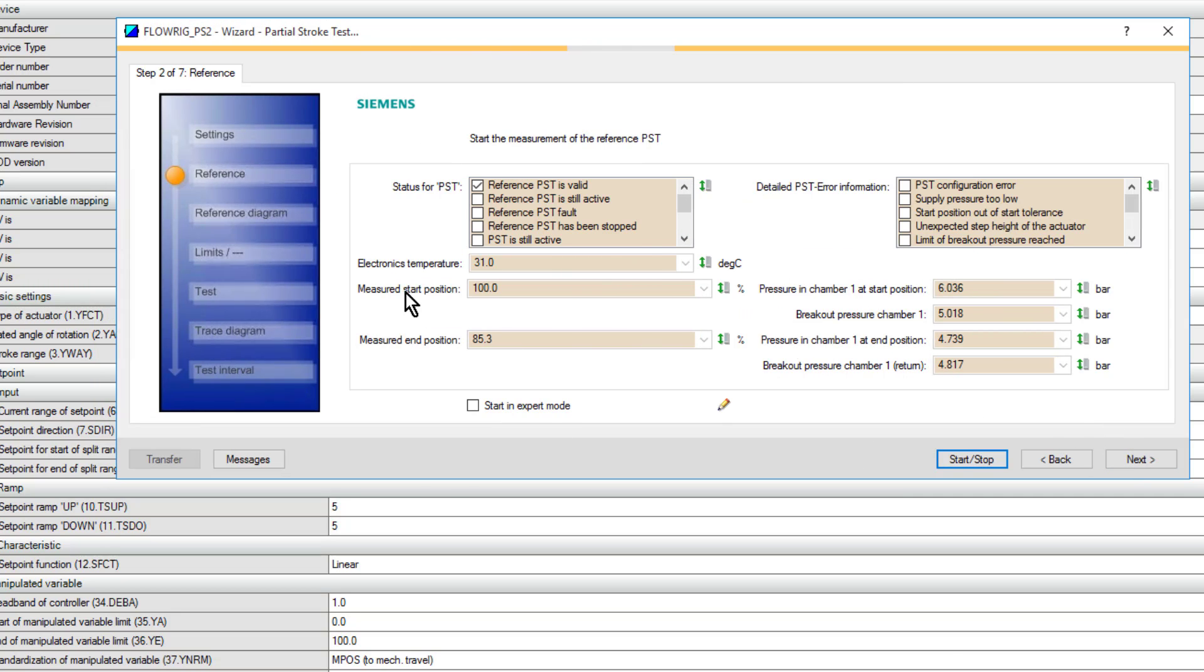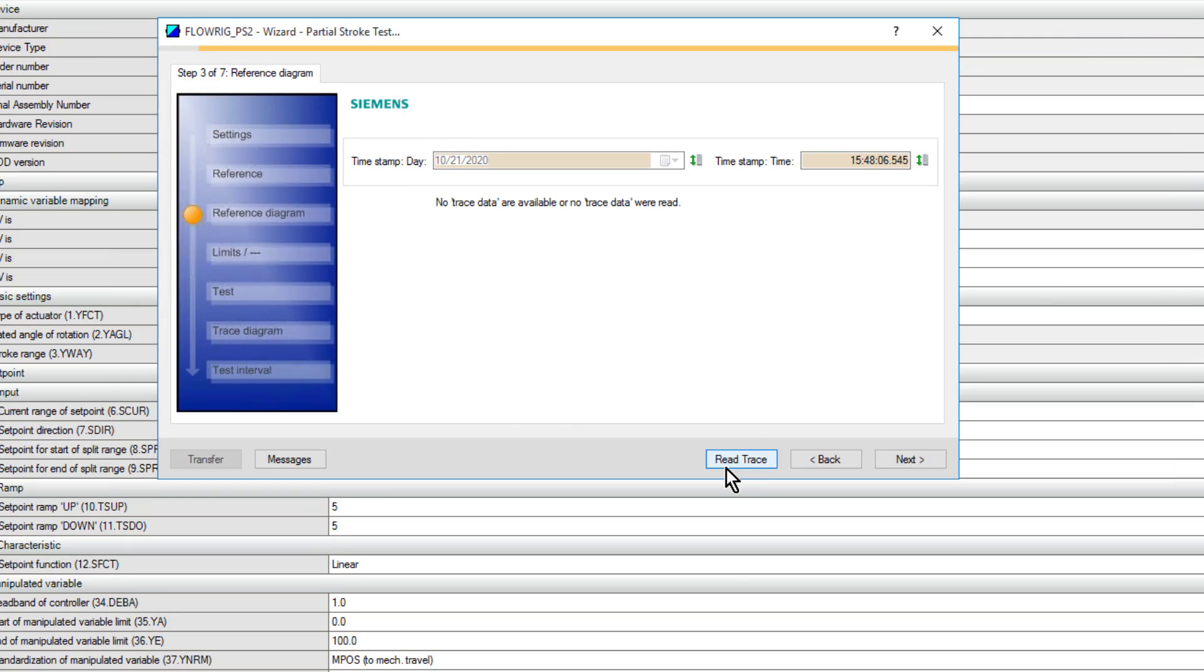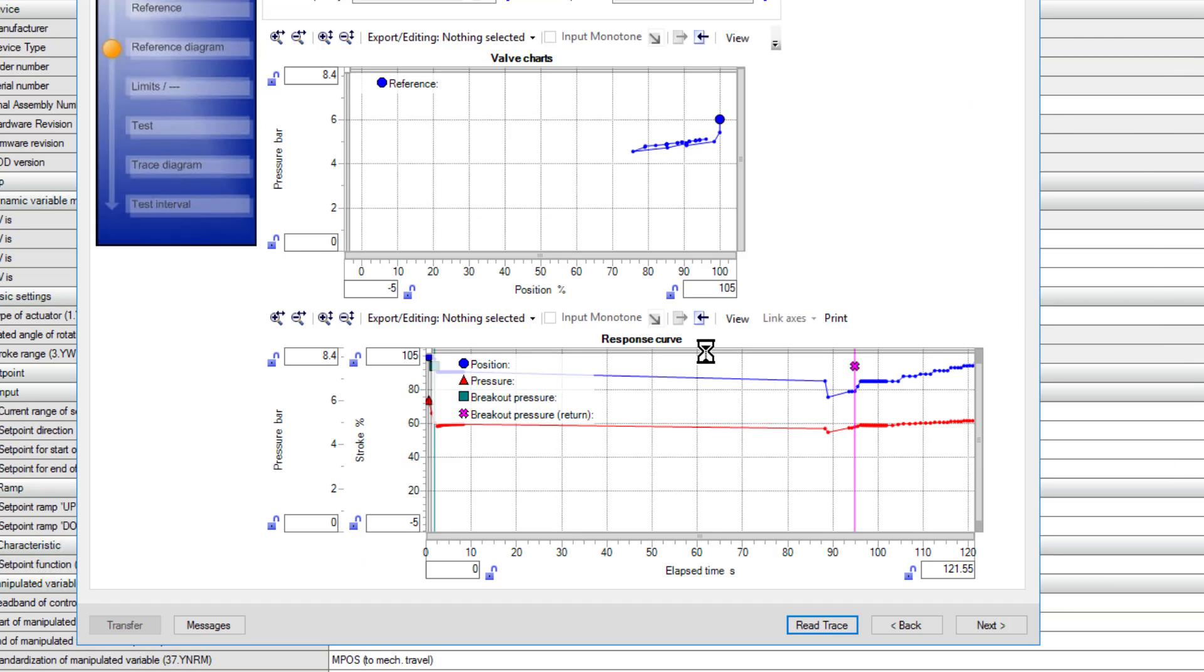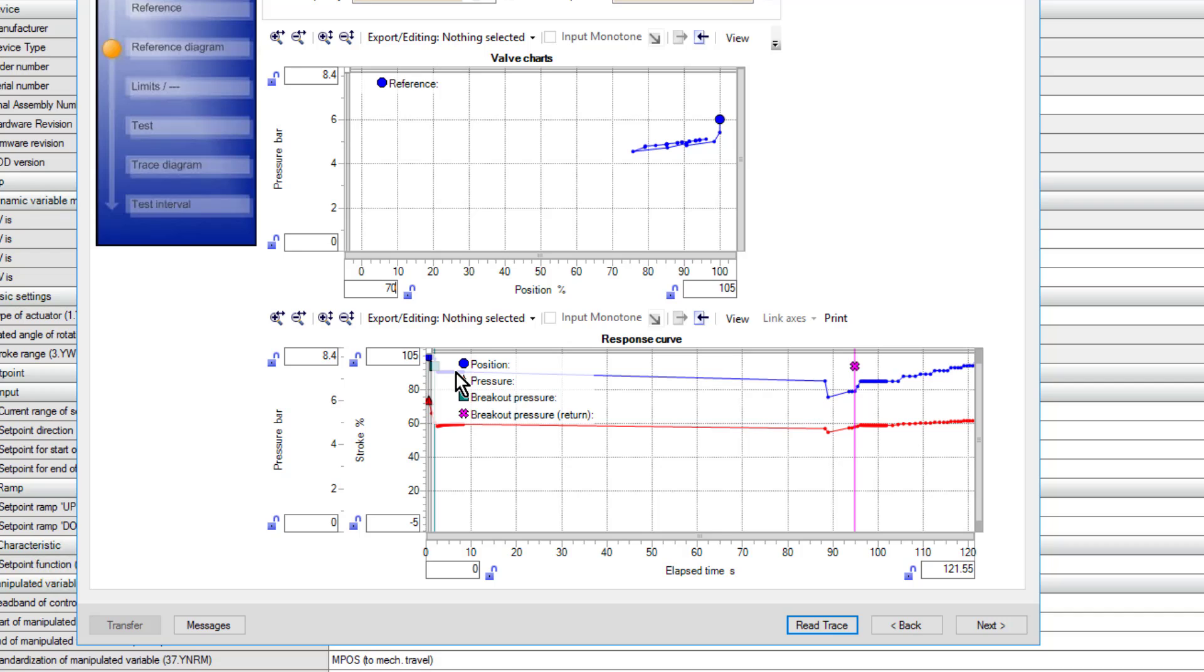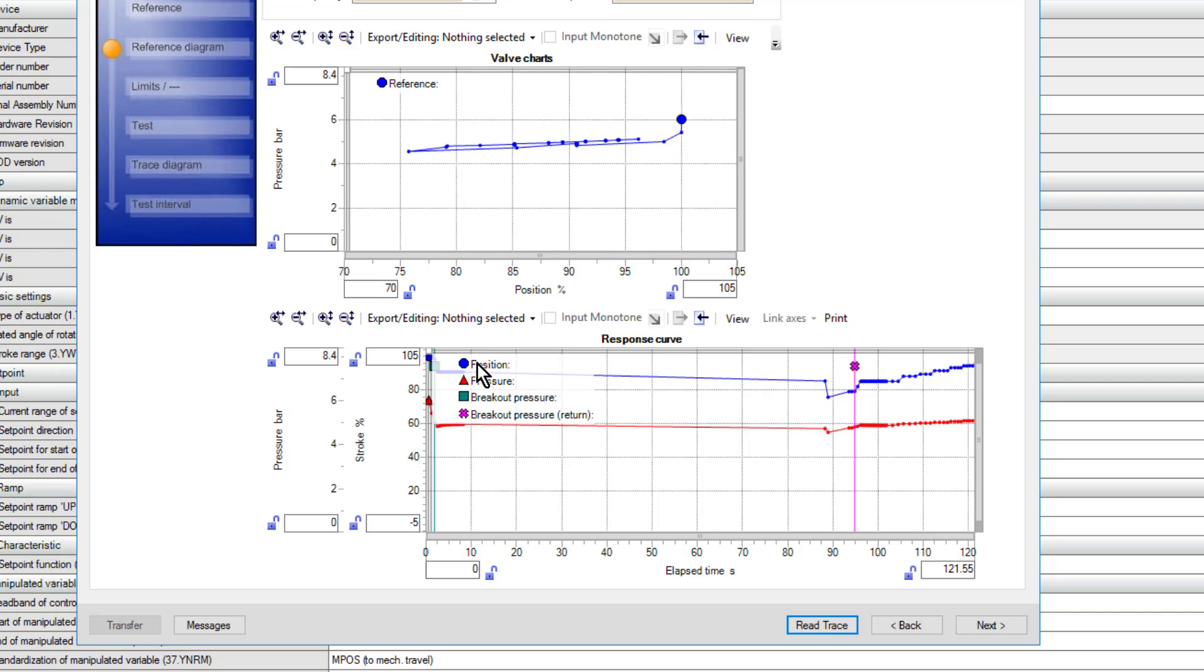Back on the standard partial stroke test window - remember we went in on expert - and now we can read the trace data. If we have a look at our trends, there's two trends on here. I'll just adjust the scale on this. This is the full scale of the valve, but we were doing a partial stroke test, so we'll just focus in on the top end. It's a little bit like the valve signature test here.